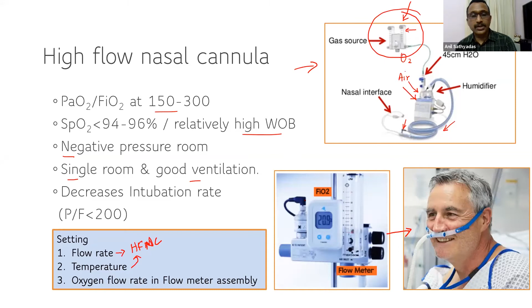You can't directly set the FiO2. That's the thing. You can increase the FiO2 by increasing the flow rate in the oxygen flow meter. The machine will tell you the temperature, it will tell you the flow rate, and it will measure the FiO2. But you can't directly set the FiO2. If you want to increase it, you have to increase the flow rate in the oxygen flow meter.